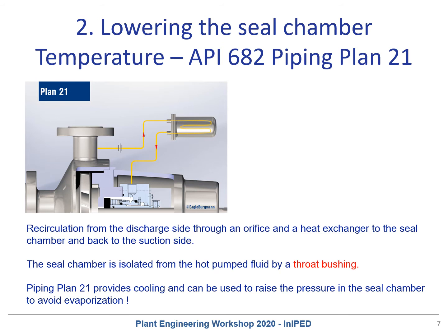Some details on option two: lowering the seal chamber temperature by piping plan 21, which is defined as recirculation from the discharge side through an orifice and a heat exchanger to the seal chamber, and then back to the suction side. The seal chamber is isolated from the hot pump fluid, ideally by a throat bushing. Piping plan 21 provides cooling and can also be used to raise the pressure in the seal chamber to avoid evaporation.